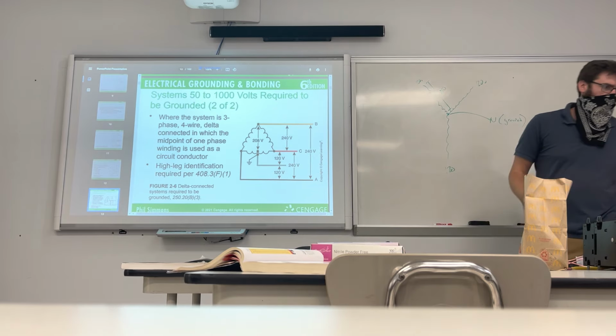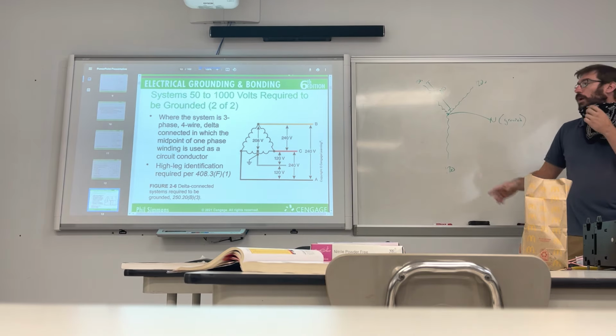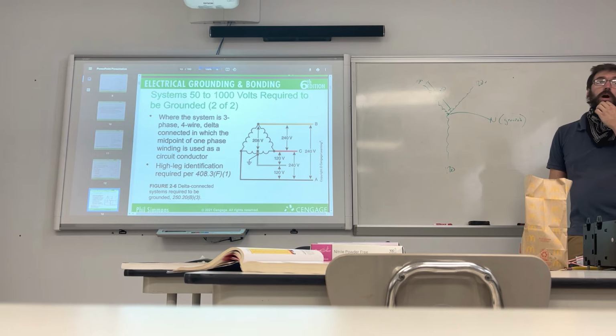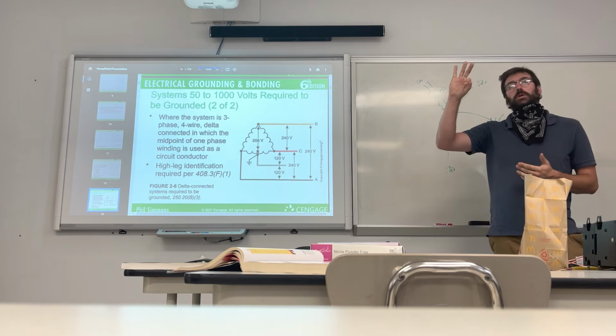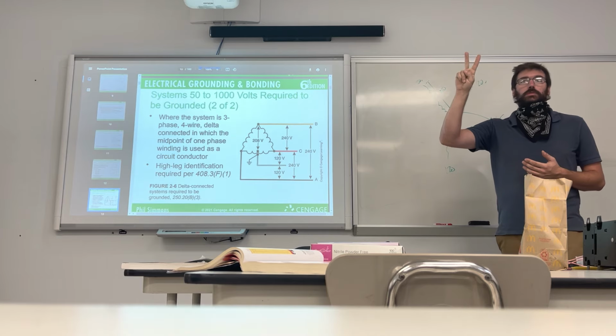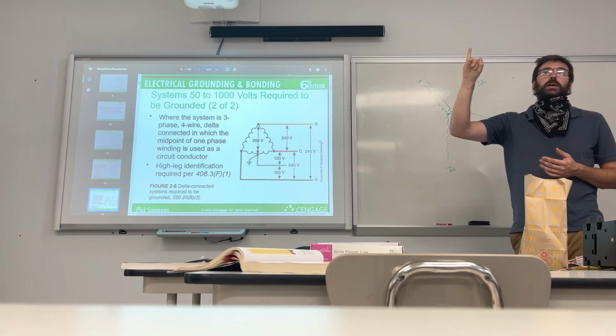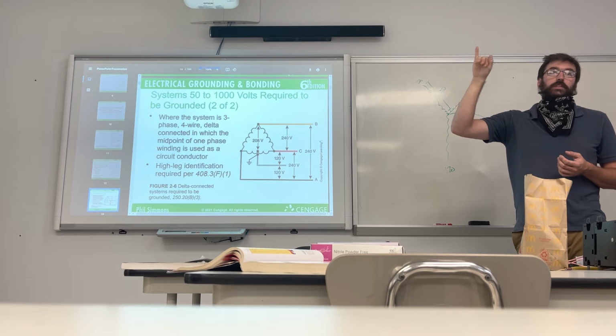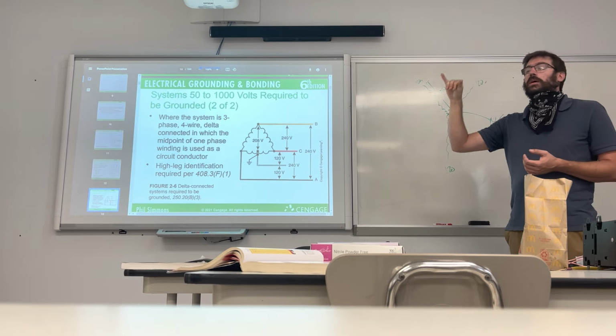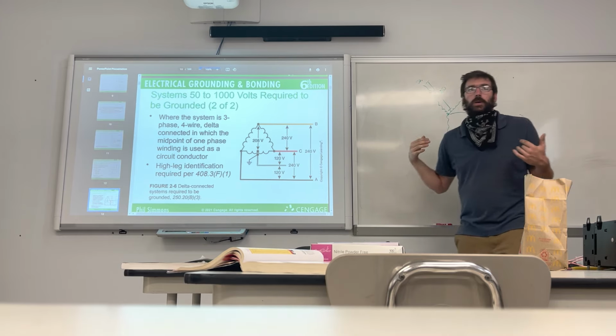And as we get further, this is very uncommon, but another very common one is called a wild leg. You'll have two 120s and one of 277. So you'll have one panel box, three poles, lines 1 and 2 are 120 volts and line 3 is 277. That's really common for a wild leg. This is kind of complicated. Let's talk about my wild leg.